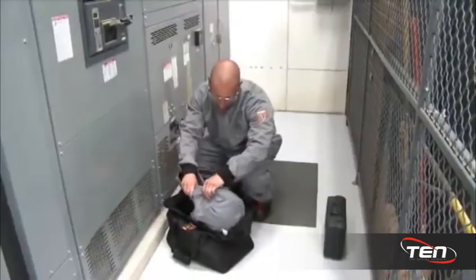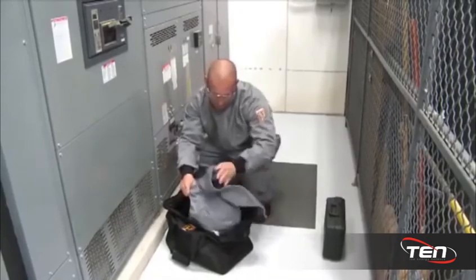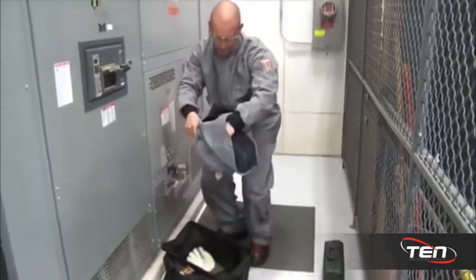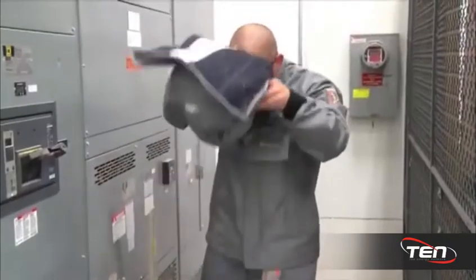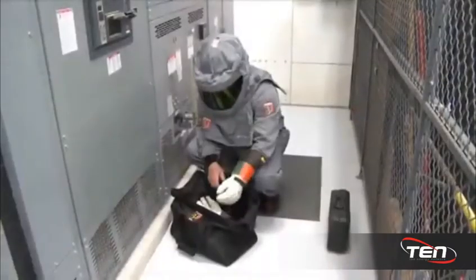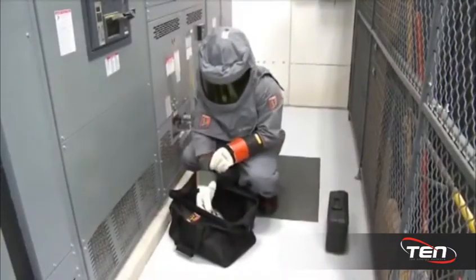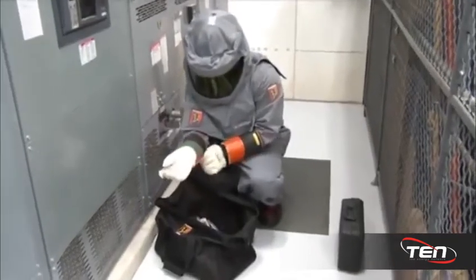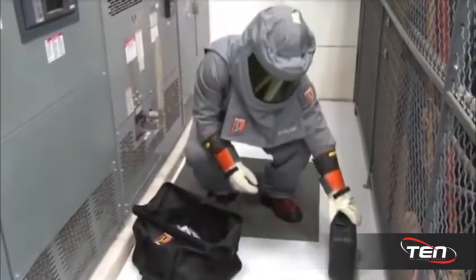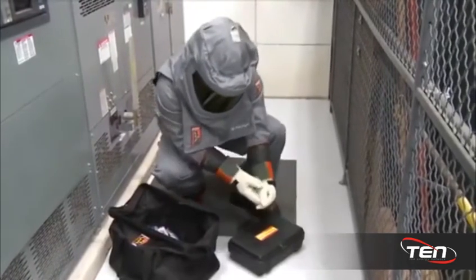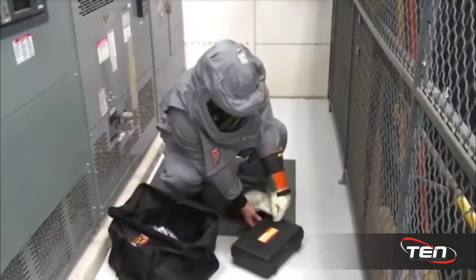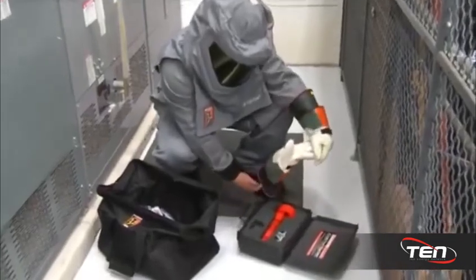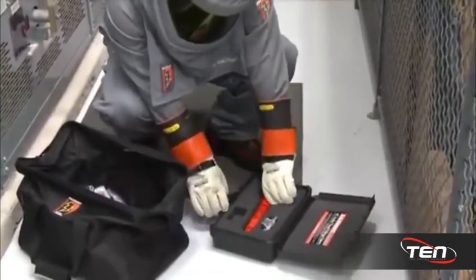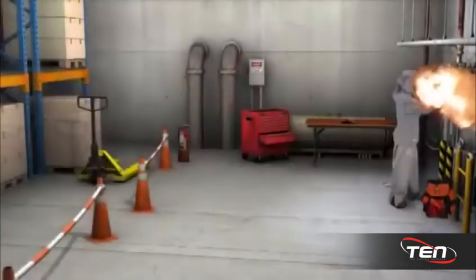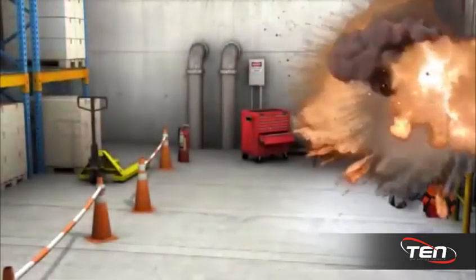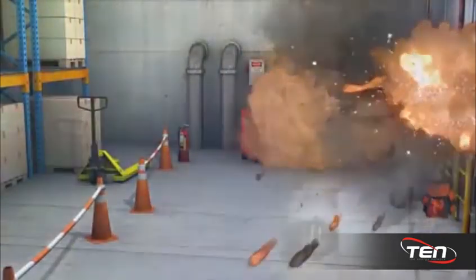The required option for Hazard Risk Category 3 and 4 includes a switching hood, such as Salisbury by Honeywell's Pro Hood Arc Flash Protection Hood, arc-rated coat, and arc-rated overalls, along with proper safety glasses, hearing protection, gloves, and footwear. These are the same items we reviewed in the last segment on Hazard Risk Category 2, but the arc rating of the material used to construct the garments and the protection values of the lenses in the switching hoods is increased to handle the increased energy associated with HRC 3 and 4 events.